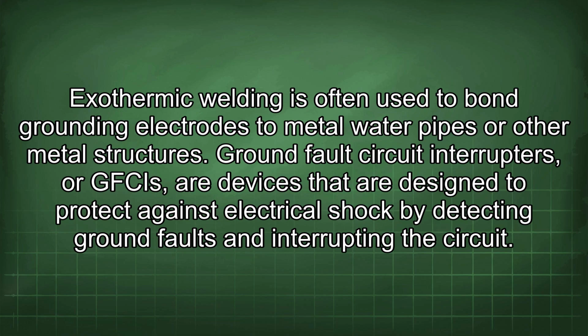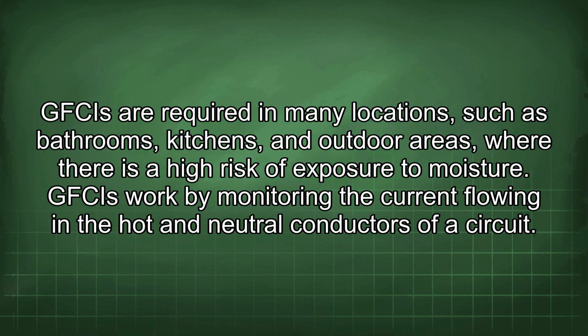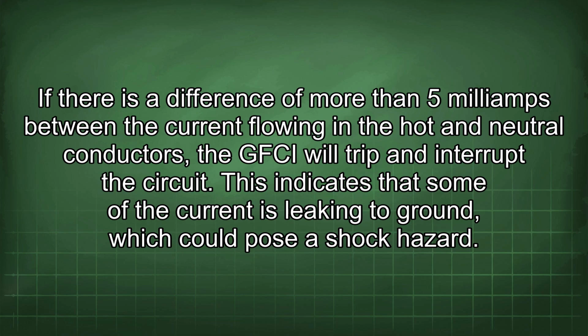Ground fault circuit interrupters, or GFCIs, are devices that are designed to protect against electrical shock by detecting ground faults and interrupting the circuit. GFCIs are required in many locations, such as bathrooms, kitchens, and outdoor areas, where there is a high risk of exposure to moisture. GFCIs work by monitoring the current flowing in the hot and neutral conductors of a circuit. If there is a difference of more than 5 mA between the current flowing in the hot and neutral conductors, the GFCI will trip and interrupt the circuit. This indicates that some of the current is leaking to ground, which could pose a shock hazard.